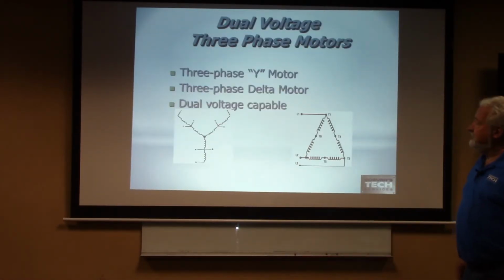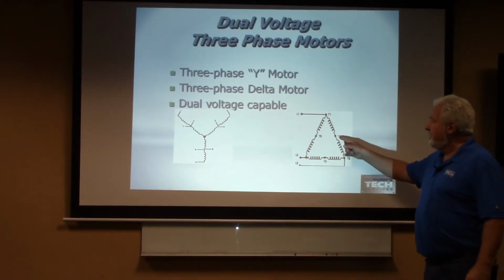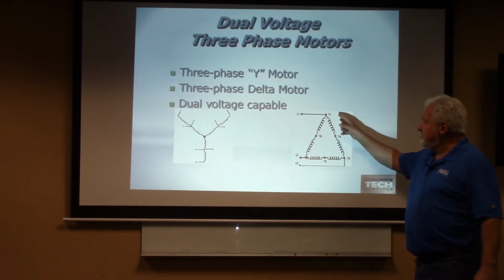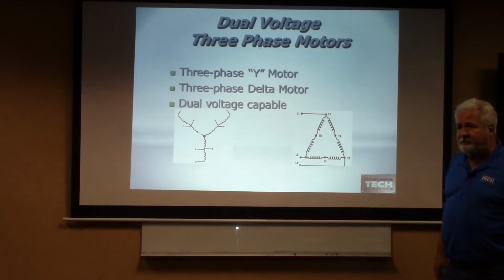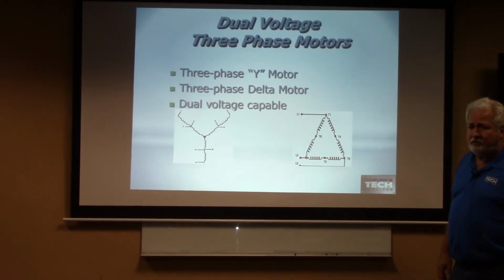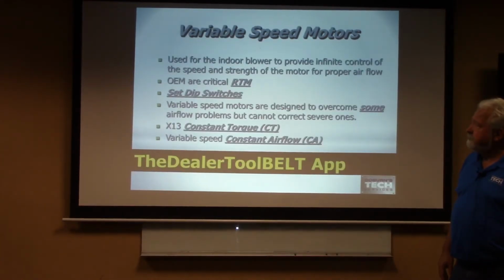All right, there's 3-phase delta, 3-phase Y. Not a lot that I can tell you about that other than they can also be dual voltage. I can either have 440 volts, I can have 230 volts to that. It's just going to be how you wire it up. T6, L1, T1, you'll wire that up separately on each one of them, and every one of those motors is going to be a little bit different.